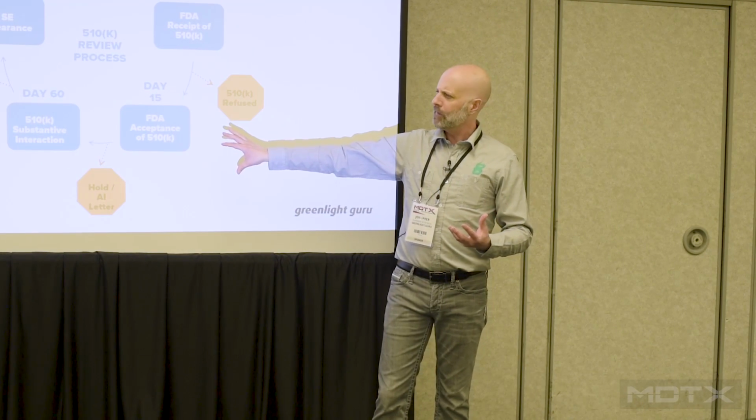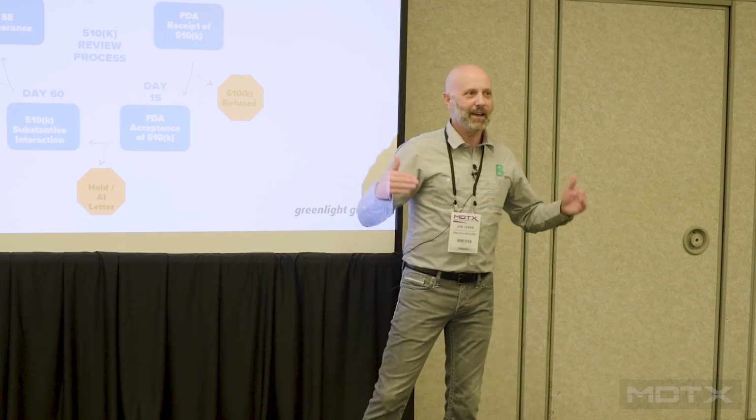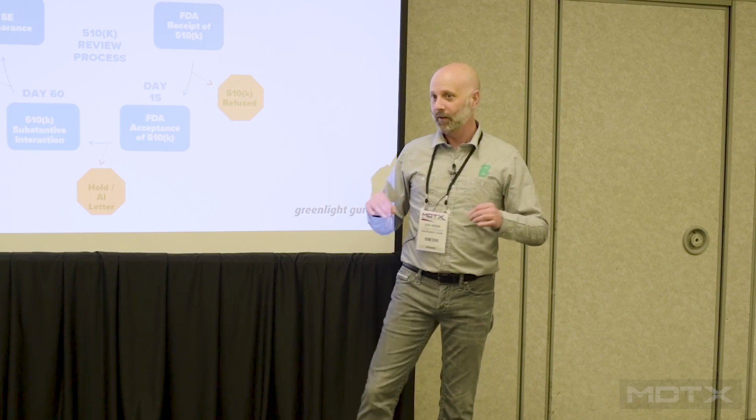They're going to say, yes, we heard you, we got your submission. Yes, we have accepted your 510K, meaning we have reviewed it and it contains the information that we expect, and now we're sending it on to the substantive review. Or, no, you're missing information, right? So if it's refused, you'll get communication. Even if it's accepted, they send you a note on that too. But it is 15 days, and they're very good about hitting that timeline. And then it gets into the substantive review, which is somewhere around day 60-ish. I mean, some of these dates are fuzzy. They're not absolutes.